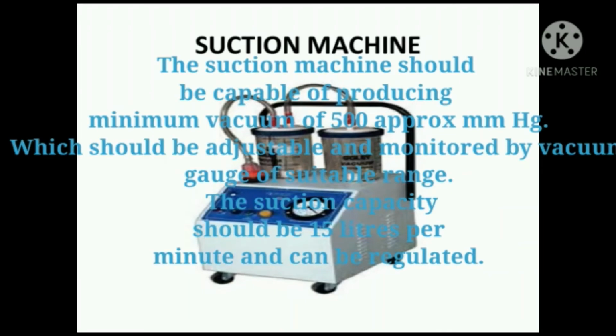The suction machine should be capable of producing a minimum vacuum of approximately 500 mmHg, which should be adjustable and monitored by vacuum gauges of suitable range. The suction capacity should be 15 liters per minute and can be regulated.